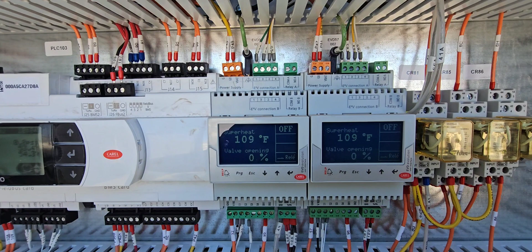But basically, they tell you your superheat. This is the main screen, superheat, valve opening, and I've already kind of scrolled through this. It shows you your wiring. This is kind of cool, it shows you the wiring for the valve. So green, brown, yellow, white, 1, 3, 2, 4. And if you look up here, green, brown, yellow, white, 1, 3, 2, 4.